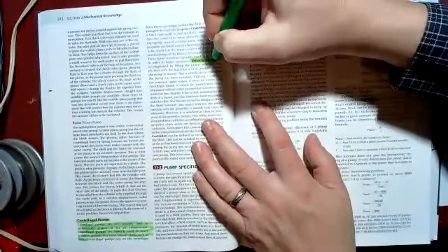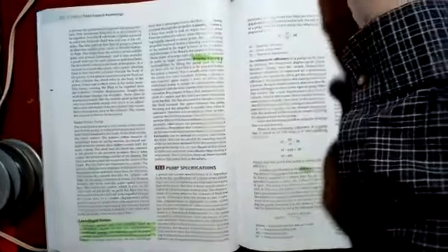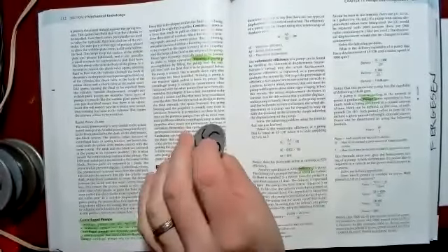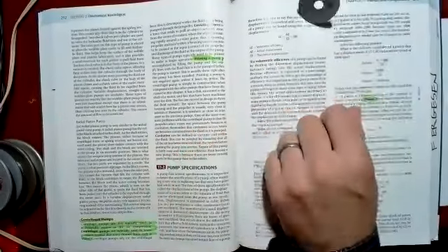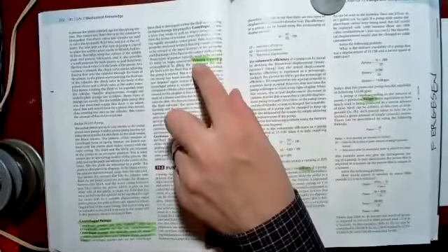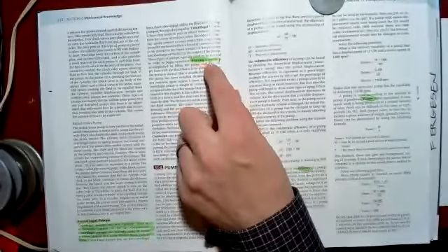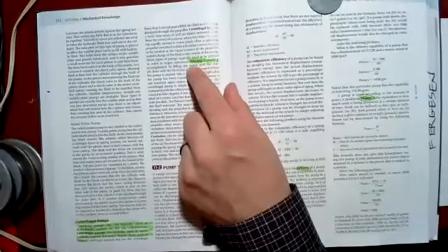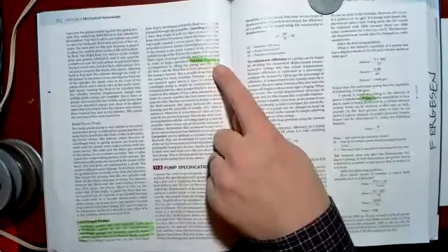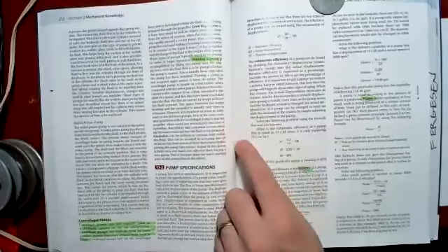Number one, you have to often prime the pump. In other words, if you don't have some liquid in that pump, when that disc starts spinning, it won't push on anything. It'll just be an air pocket around the disc, and the pump won't do anything. All right? So you often need a way to get liquid into the pump to start it running to create enough pressure to pull more liquid into the pump, or vacuum in this case.